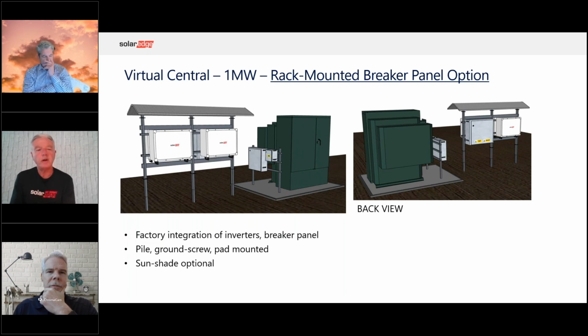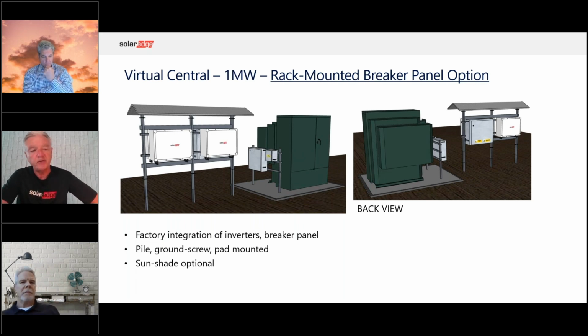So the virtual central inverter that we are advocating is the 1 megawatt and the 2.5 megawatts. What you're looking at here is the 1 megawatt, and this is where you have 3 inverters and a box with 3 circuit breakers in it, also mounted on this rack.